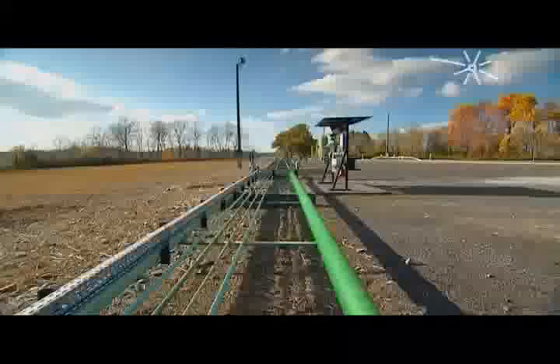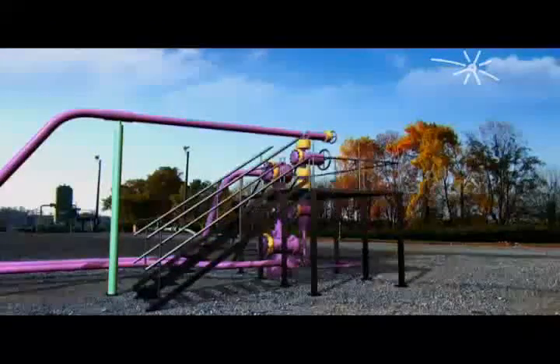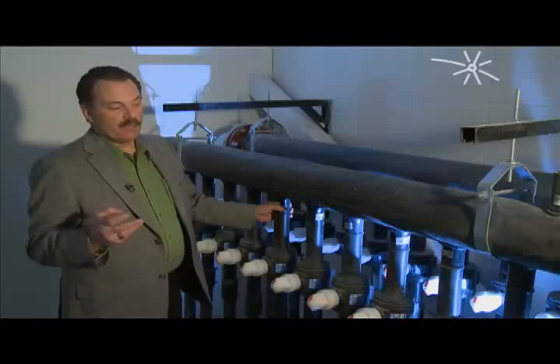In the mechanical room here we have built what we call a header. What we're dealing with here is two groups of 10 pipes coming from the ground. One group will be what we call a supply, the other one will return. So as we're circulating fluids through the ground to absorb the energy from the ground, there will be one pipe that goes down a hole and another one that comes back up.